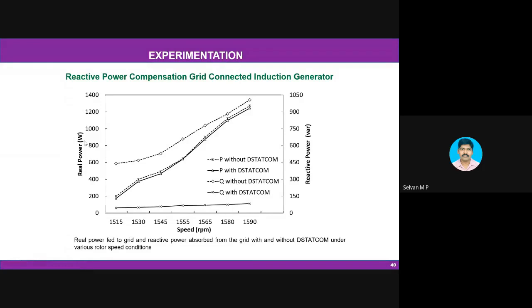Tamil Nadu wind capacity is around 8000 megawatt. So in order to generate 8000 megawatt, approximately you have to supply 6000 MVAR. From where will you supply 6000 MVAR? It will be very difficult. So the wind operators are requested to have their own capacitor compensation. Otherwise they will be punished. But the capacitor will not be able to provide complete compensation when the voltage goes low. So the machine tries to draw from the grid, and the grid is getting additional burden. In order to avoid that, we can go with the STATCOM.